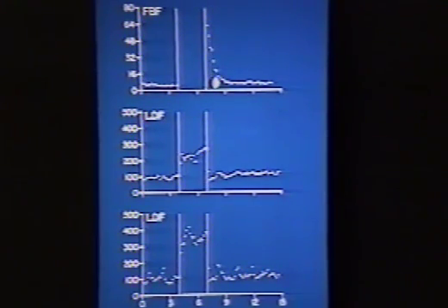And then to see what happened with the laser Doppler signal. During the exercise, we see a large increase in the signal. That's not blood flow, that's noise. This underscores the problem of motion artifact. These are overlying the active arm, and so it precludes the use of the laser Doppler for making measurements of blood flow to skin over active muscle.